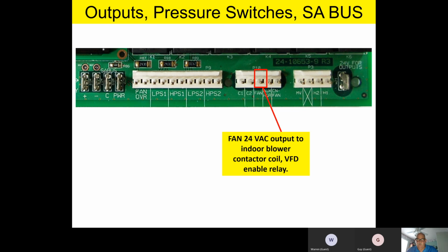Next to that is a 24-volt output to our indoor blower. Now this is important. If you've got a conventional, just a three-phase belt drive motor in there, not a variable frequency drive, just a motor, this is going to output 24 volts to the indoor fan contactor. This is the control voltage for the contactor.